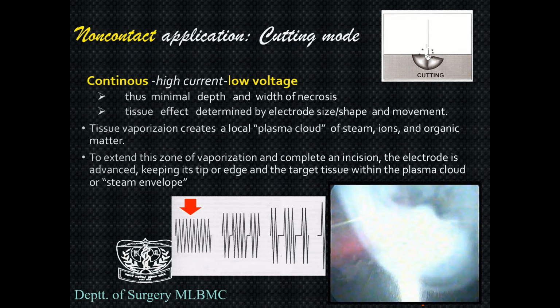Now, we've been talking about non-contact and cutting mode. So what do these really mean? When we talk about non-contact, we are basically saying that your probe tip is never in contact with the body. This is the body, your probe tip is not there. So when you're using non-contact, you can cut the tissue or you can coagulate the tissue. Now continuous high current, I just now showed you the first figure. So here also low voltage. Continuous low voltage, high current basically means high amperage. Why? Because it's constant. The current starts here and keeps on flowing. So obviously it has to be high amperage.